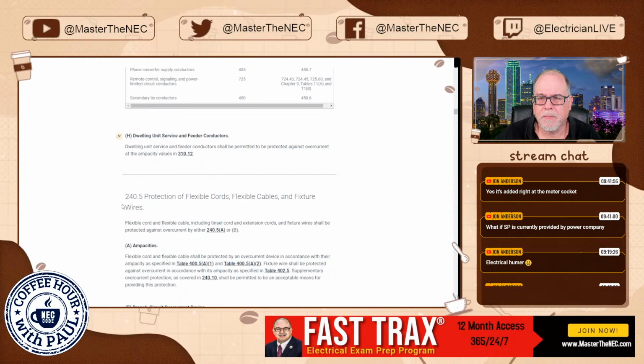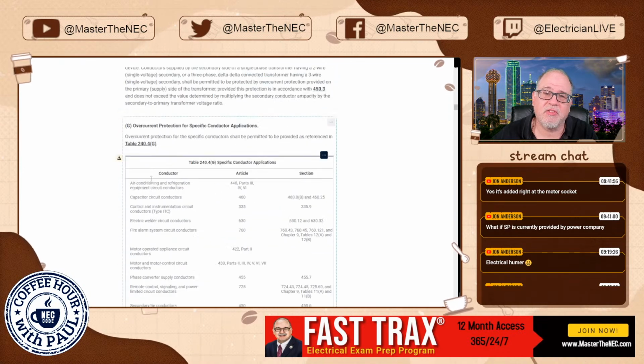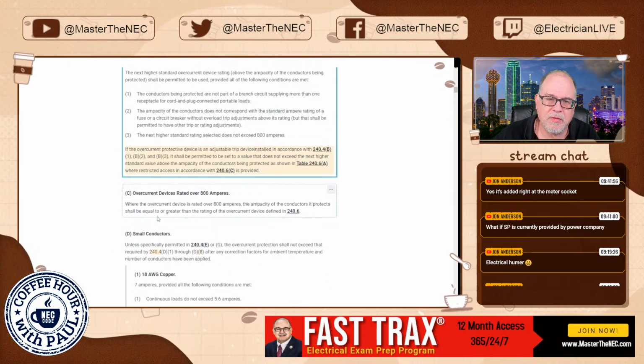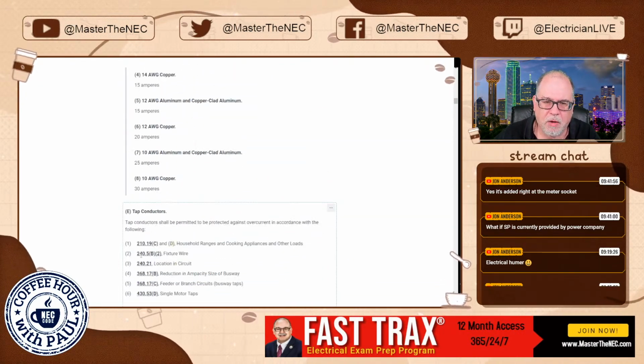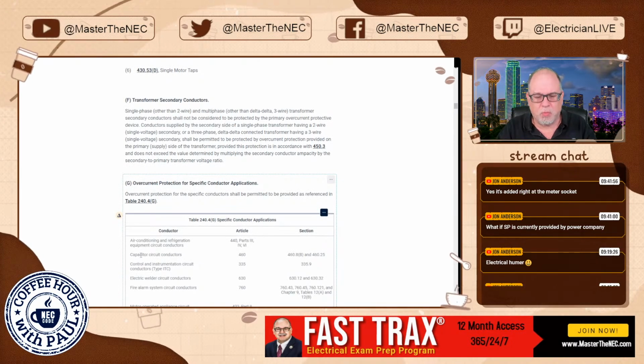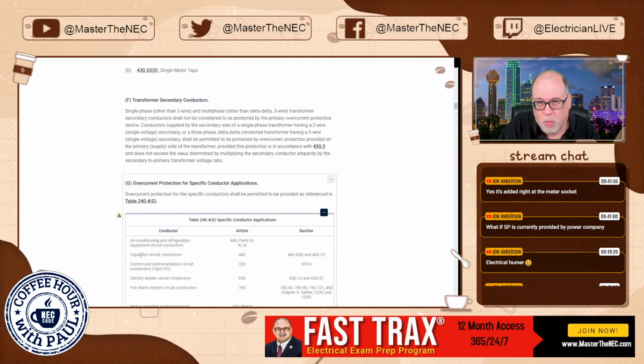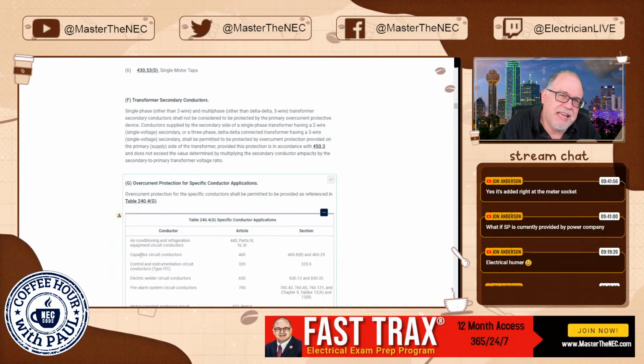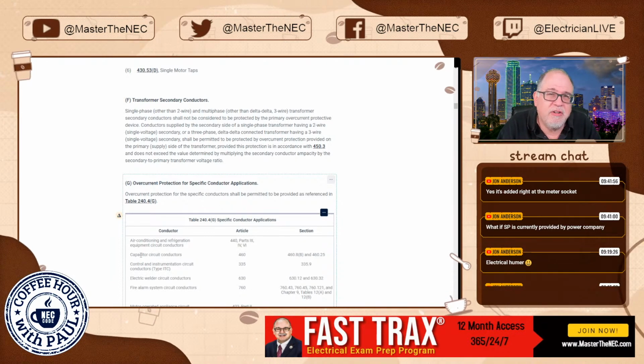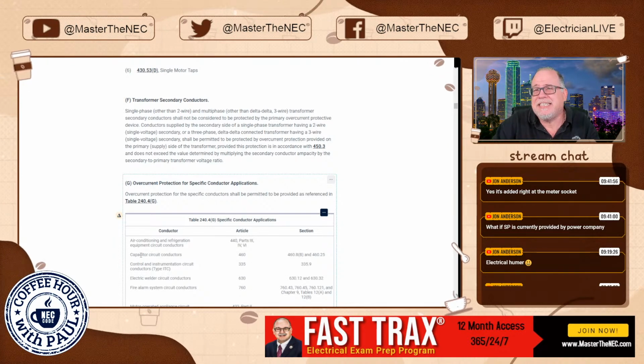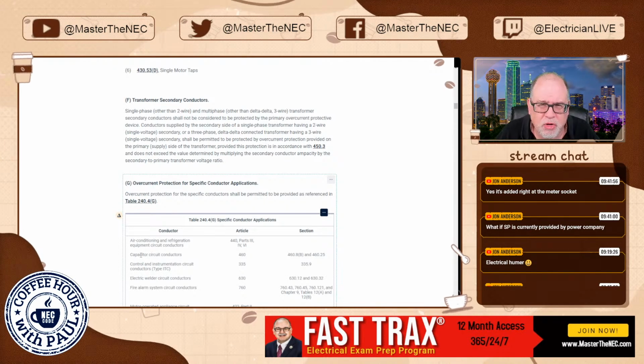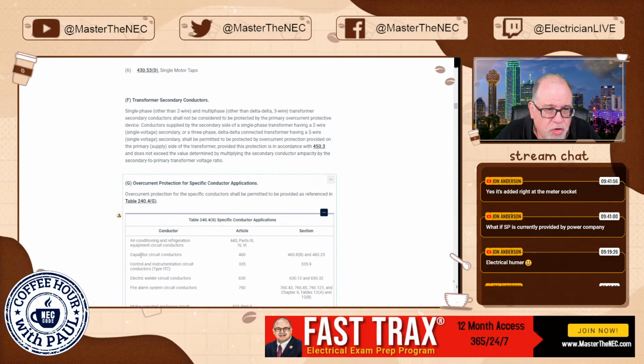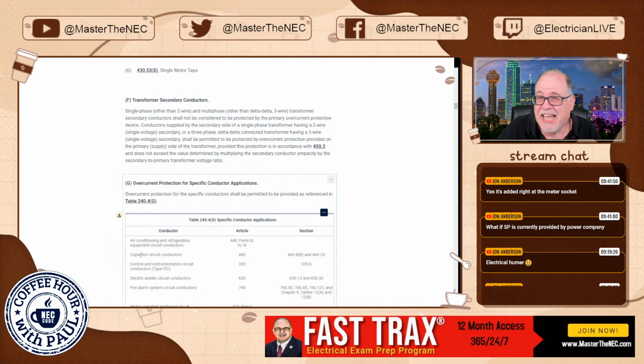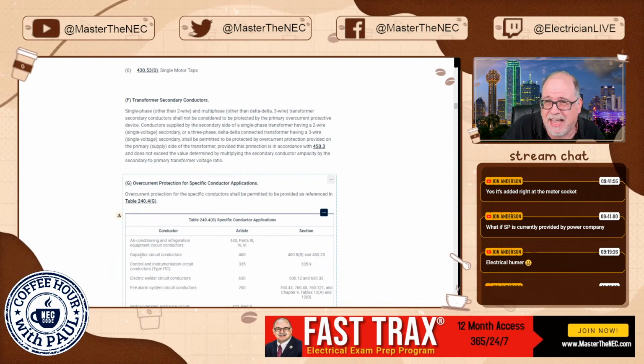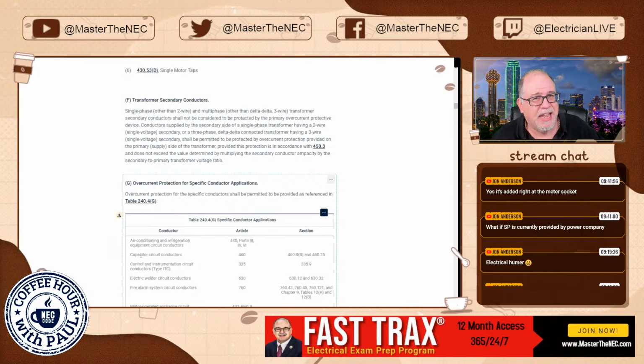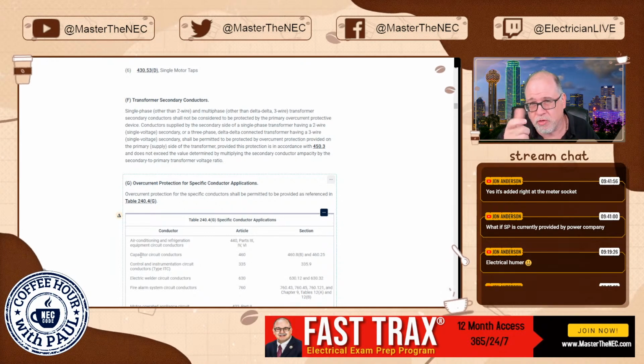Let's see here. Oh, so here is H. Now let me show you back what we've got here. So you have these rules here for protection of conductors. Now, we know that the 83% rule, which is where if it's not over 400 amps, if it's 120/240 volt, things like that, then we have the allowance for service conductors and feeders to not have to be larger than 83% if you meet all of the conditions that are in 310.12, right? Referred to as the conditional smaller service conductor rules, right? And the table for that came back into the code in the 2020 edition. Previous to that, it was back in Informative Annex D, right? And we just had to do the math, the 83% of whatever the service or feeder rating was. That's whatever's on the circuit breaker.